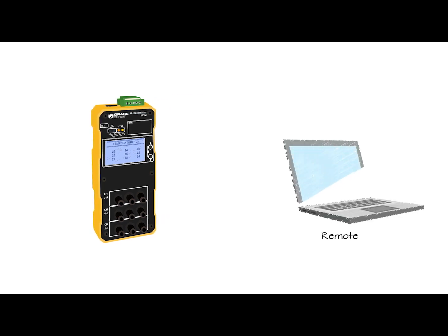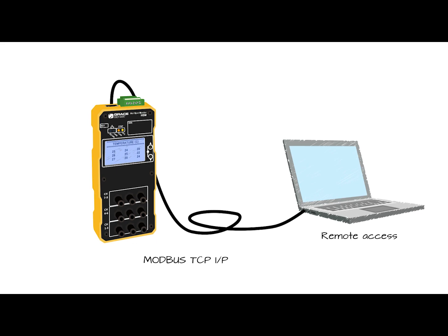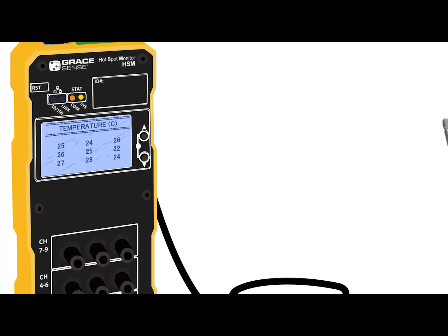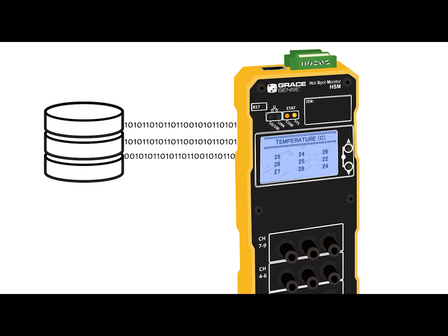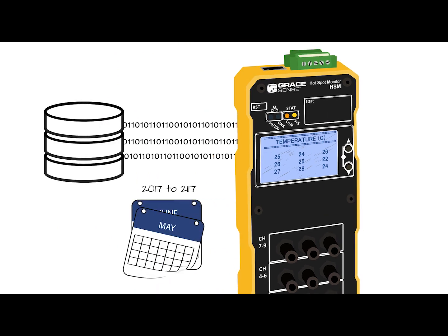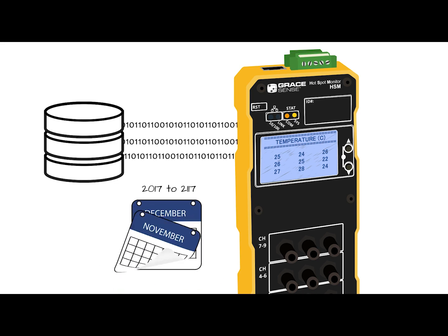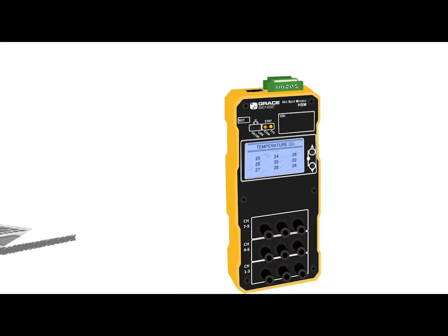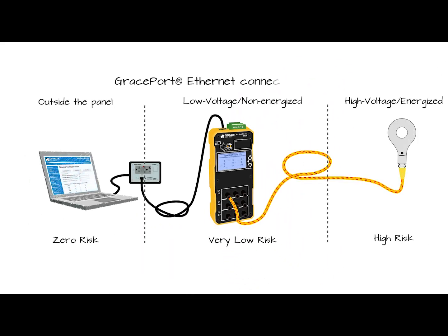By connecting the GraceSense HSM module via Modbus TCP/IP or Ethernet IP and accessing the web utility tool, users can configure the temperature thresholds, time intervals, and relay outputs. This tool further enables access to the real-time data logs and downloads the stored data for analysis and trending, connecting directly to the device or safely through closed doors using a GracePort Ethernet connector interface.